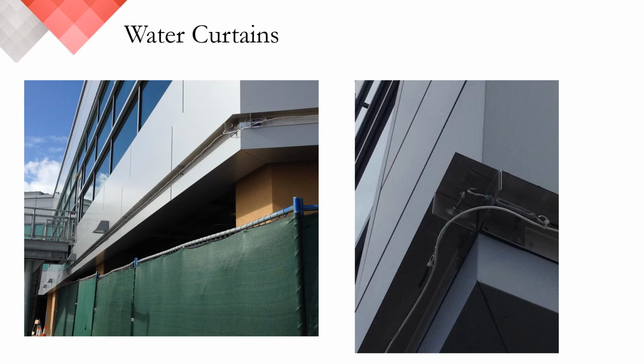In these structures, the potential for fire is most prevalent in the area below the overhang. In this image, we see linear heat being applied directly above this area, along the lower ledge, and utilizing a messenger detector to span the distance, and providing a great transition around the corner. Again, our 2.5-inch bend radius is crucial. Taking the time to assure a smooth transition will make sure that you have reliable service.